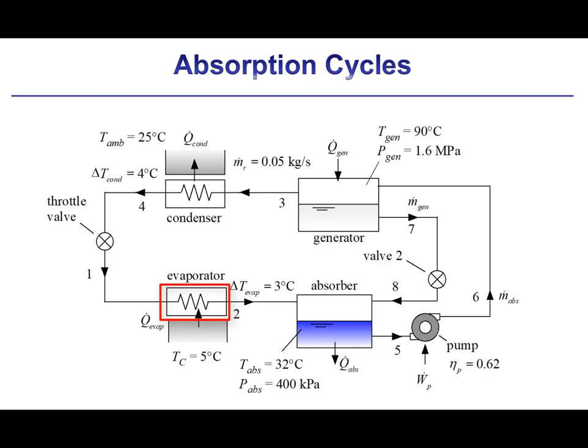The condenser rejects heat to ambient at 25 degrees Celsius and it has an approach temperature difference of 4 degrees Celsius. The evaporator removes heat from a space that is at 5 degrees Celsius and it has an approach temperature difference of 3 degrees Celsius. The absorber operates at 32 degrees Celsius and 400 kilopascals.